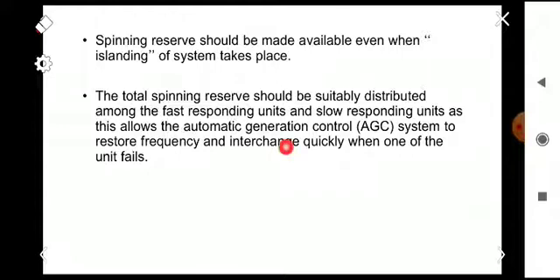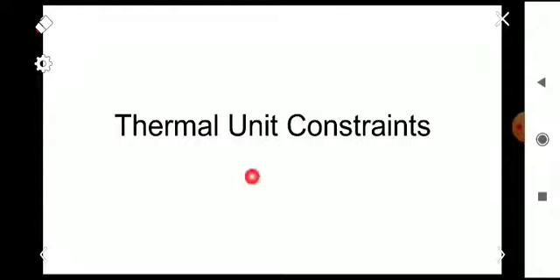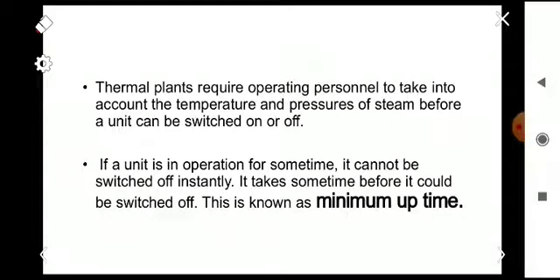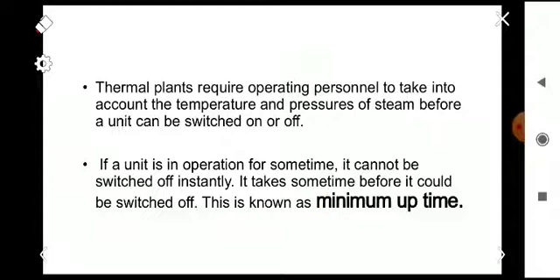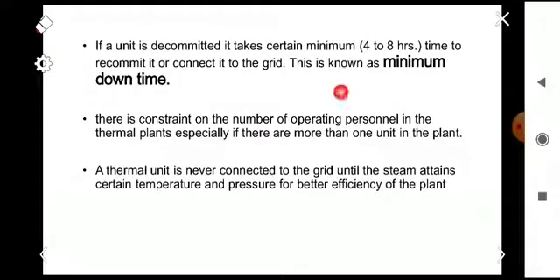The next constraint is the thermal unit constraint. Thermal plants require operating personnel to take into account temperature and pressures of steam before a unit can be switched on or off. If a unit has been in operation for some time it cannot be stopped instantly — it takes some time before it can be switched off. This time is known as minimum uptime. Another constraint is the minimum downtime.